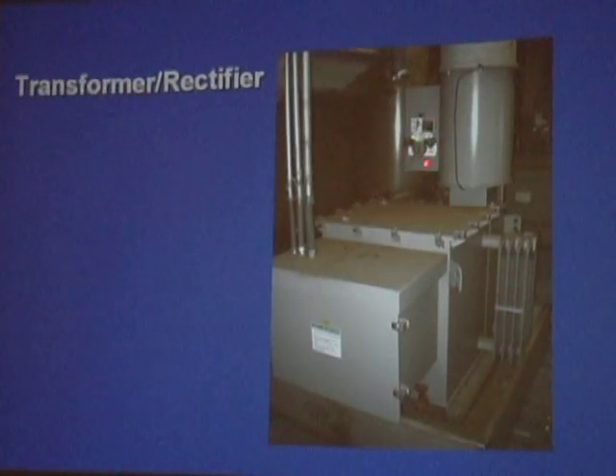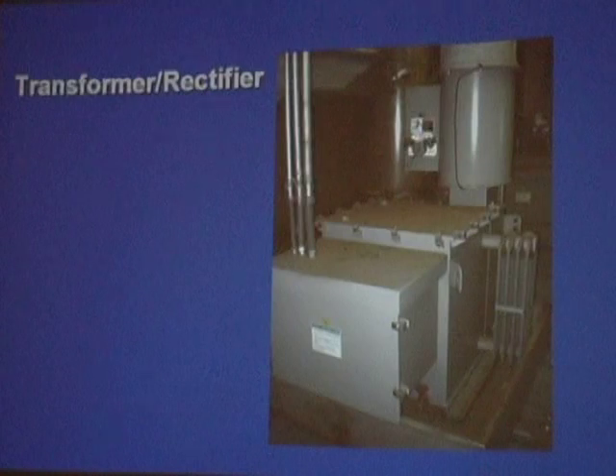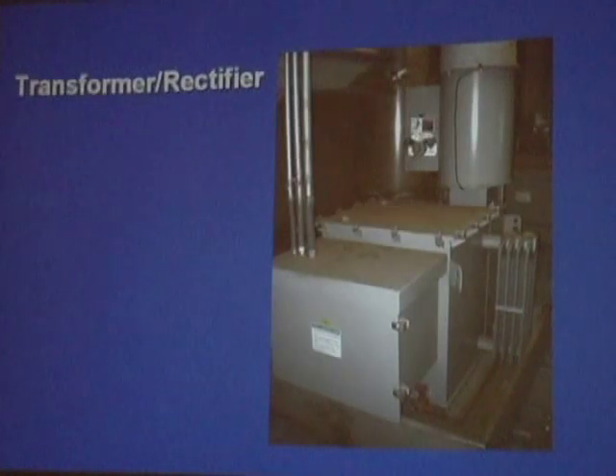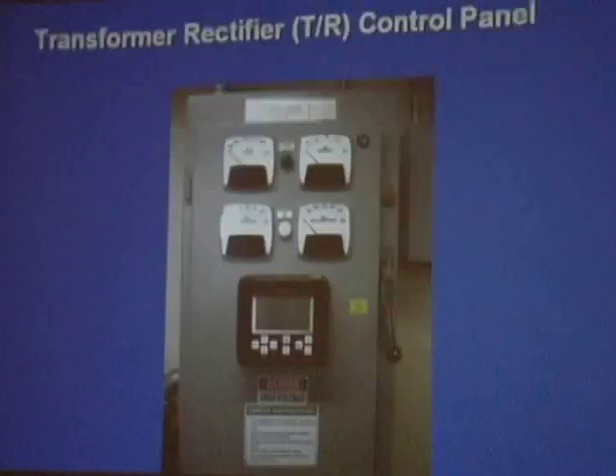Safety aspects of this: you are dealing with high voltage charged elements, so whenever you go in to service this thing, you have to make sure that everything has been grounded out and secured. And if you go into the actual grid section where the probes are, there's a grounding stick that he wants you to use to ground out the system before you do any maintenance. There's a key system too.